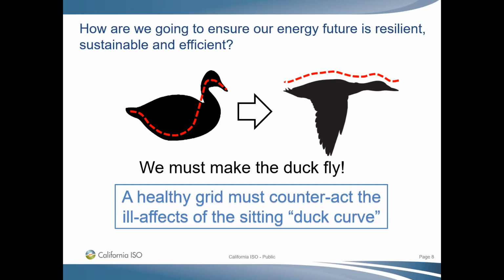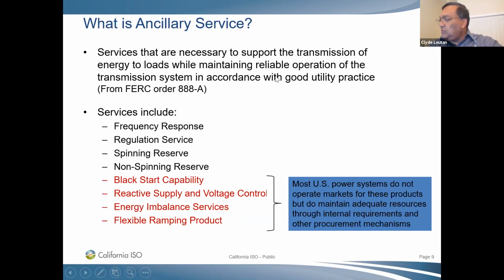That's all for now. Okay, so moving along, ancillary services, and most of you know what ancillary services are. Essentially, it is the necessary support that we need on the transmission to ensure that you can transmit that energy to load and at the same time meet reliability and safety, and you need to do all of that in accordance with good utility practice. As I mentioned, if you have too much generation on your system, you cannot allow that excess energy to flow into your neighboring system. You've got to contain that, or do the best you can to contain that within your system. So that's one of the big differences, and what makes it a challenge to integrate renewables in the US.